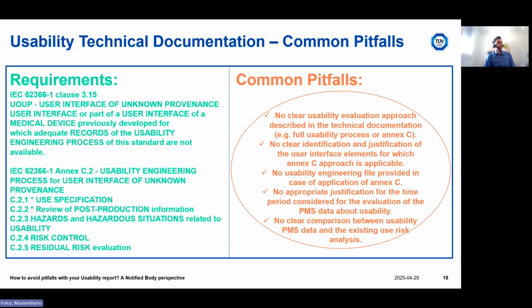The alternative approach is described in Annex C in 5 steps. The first one requires defining the use specification as for the full usability evaluation process. Then the manufacturer has to review the post-production information related to usability, choosing an appropriate time period that is not defined in the standard.